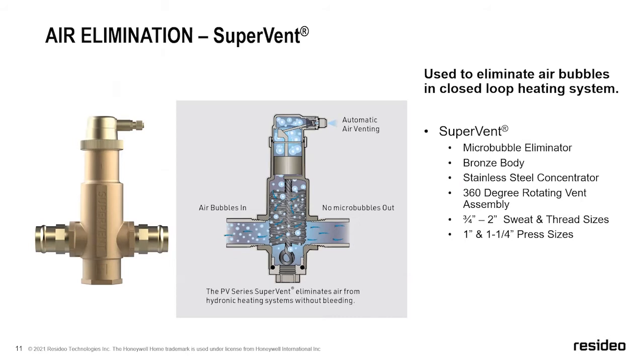Looking at our SuperVent, we have two different air elimination devices in our product portfolio. We have the old school air purger, or sometimes they're called air scoops. I'm not going to talk too much on those. What I did want to bring light to is our SuperVent that we've had for a long time. The way this works is essentially your water and air mixture passes through the coalescing media on the inside, which ours is very similar to almost looks like a stainless steel brush. As the air bubbles pass through, they stick to all the little bristles on that brush. When enough of them stick together, they're going to float up to the top. They're going to get up to the top of that air vent and push the float down when enough of them collect.